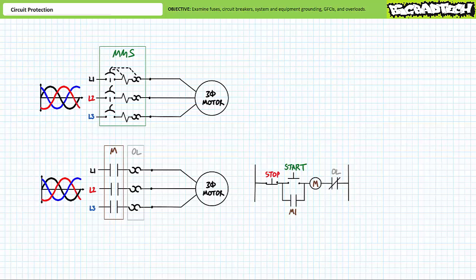Overloads, regardless of the means of operation after being triggered, need to be reset for the device to operate again. The overload, like a circuit breaker and unlike a fuse, is a reusable device. Sometimes this reset is performed automatically or must be done so manually, requiring human intervention. The time period between triggering and automatic reset allows the overload element to cool. Due to the cumulative nature of heat, overloads that have been triggered once will trigger earlier subjected to the same overload. Repeated overloads are a clear sign the motor is undersized for the task. Do not think for a moment we're done discussing the overload relay. We'll return to a far more thorough discussion of motor starters, contactors, and overload relays in much later lectures in motor controls.